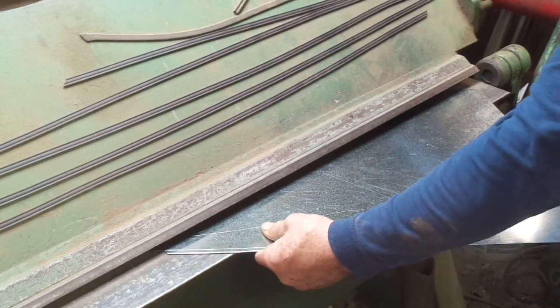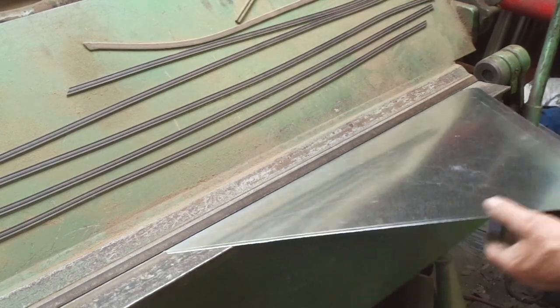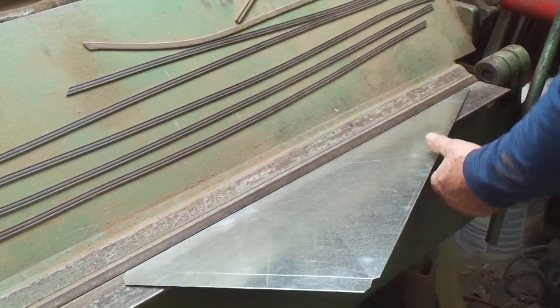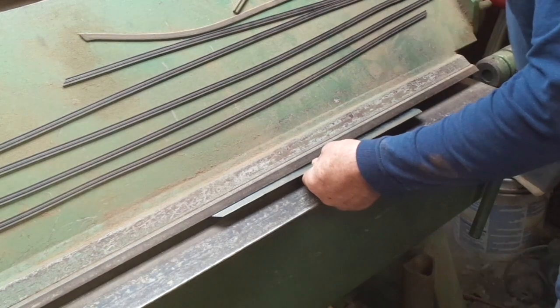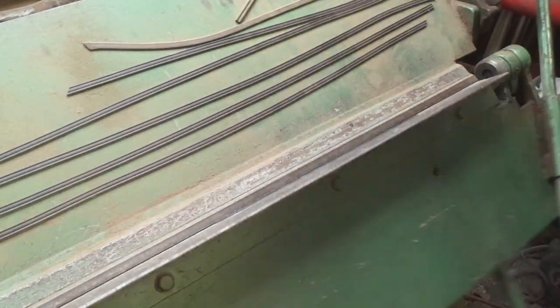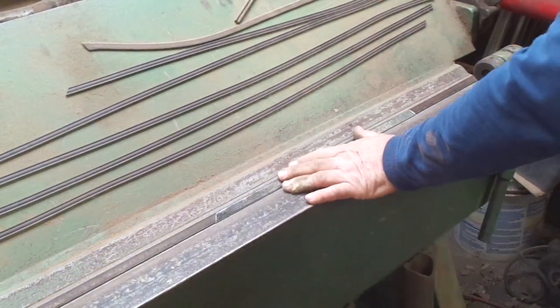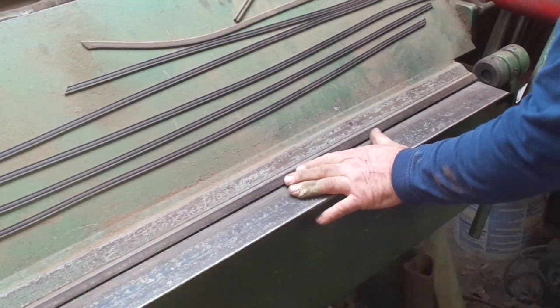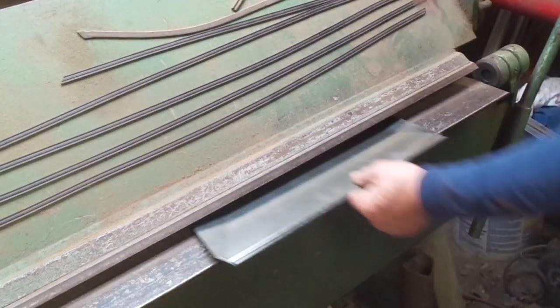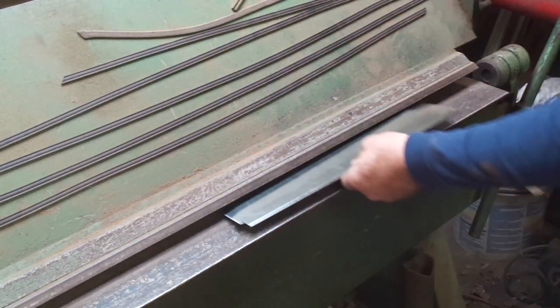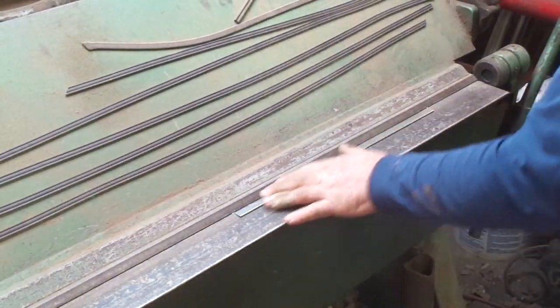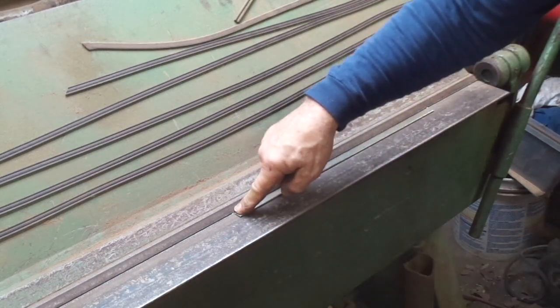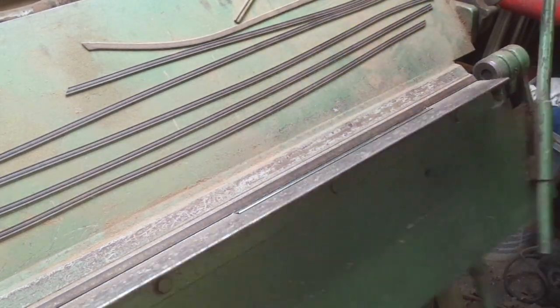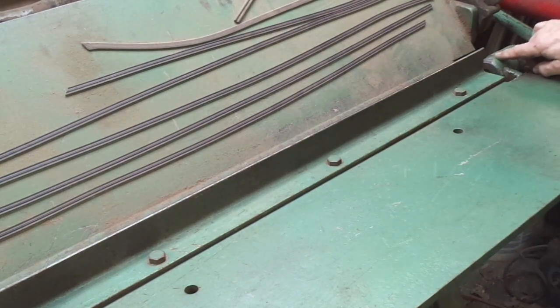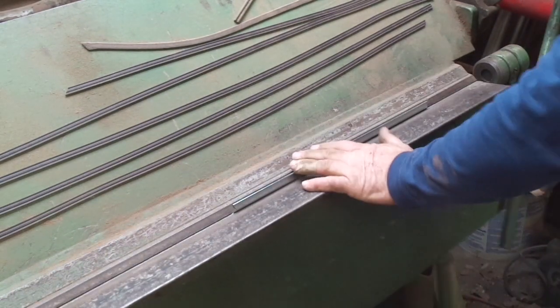First thing I like to do is go ahead and get my cross break in, if the material requires a cross break. Then I like to go for my double hem flange, slide right into the half inch mark, fold that up as far as it'll go, give it a slap. Don't have to latch it completely down. Turn her over and get your 90. Make it a crisp 90 right at the juncture of where you notched from both sides. Again, you've got your scale over here if necessary to tell what angle you're folding at.